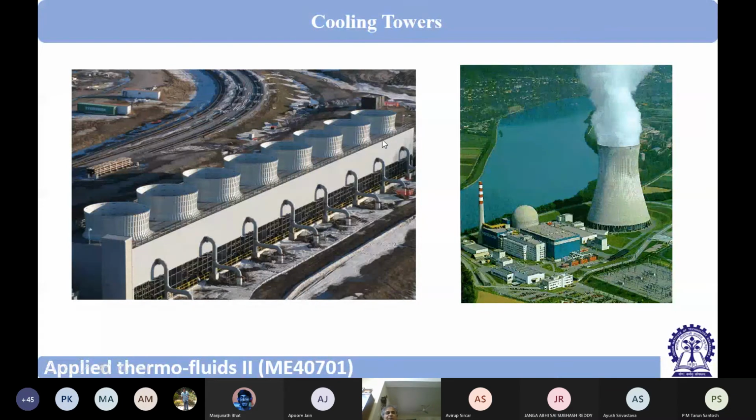So, cooling tower cell. If necessary, 1 or 2 you may not operate. You can separate it. And there could be a valve. So valve you close, fan you close. So depending on your requirement, you can add a number of cells or not operate a few cells.